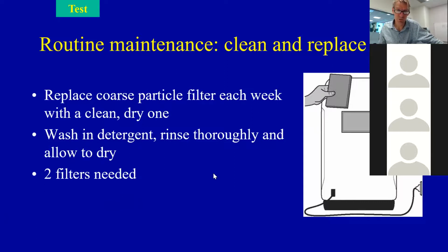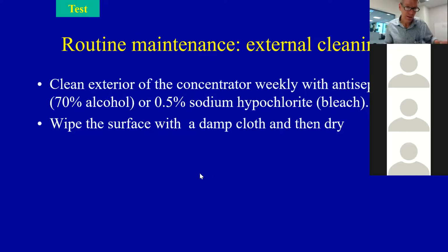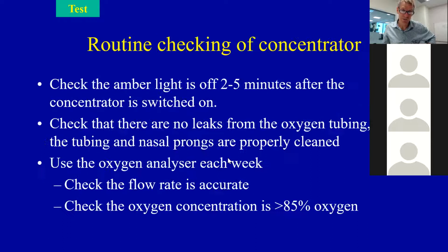That's the external coarse particle filter. I think you should clean the concentrator every week because it can get dust on it. So I clean the exterior of the concentrator with an antiseptic, like 70% alcohol, which we're used to using, or 0.5% sodium hypochlorite, which is just bleach. It's a chlorine-based cleaning fluid that'll certainly clean any viral particles or bacteria off the concentrator. You wipe the surface with a damp cloth and some antiseptic, and then dry the concentrator. You should have a program of cleaning your concentrators regularly, every week at least.